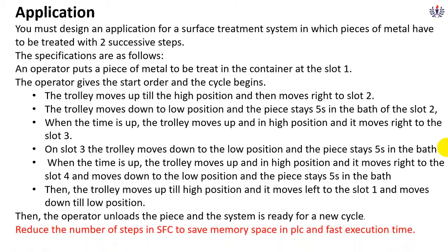This application is similar to application 1B, but one thing we are going to do here is reduce the number of steps in the SFC, which can save memory in the PLC, and it has a faster execution time, because we might have studied the PLC scan. PLC scan can be defined as the summation of the input scan, program scan, and output scan. Similarly, that scan time will be reduced, so the execution time will proportionally be reduced. That we are going to see here.